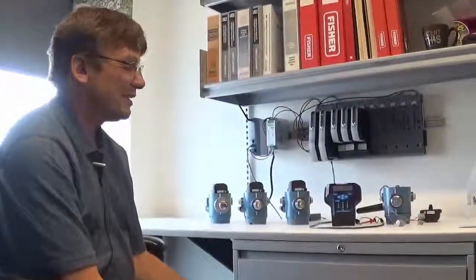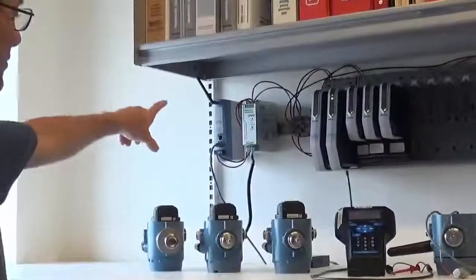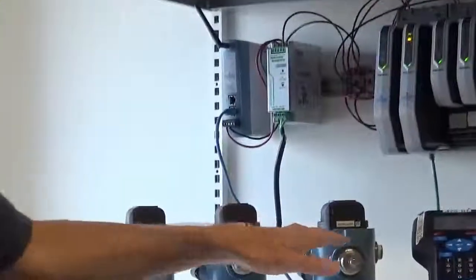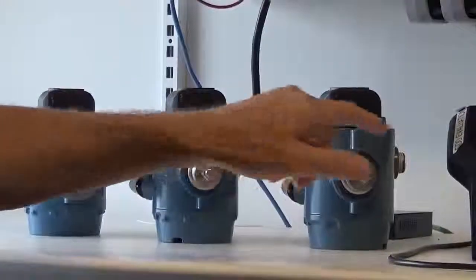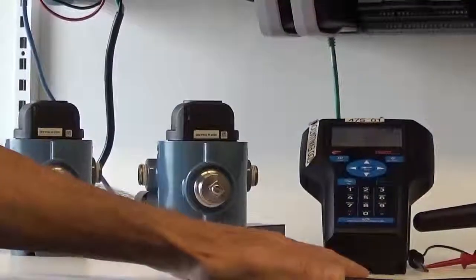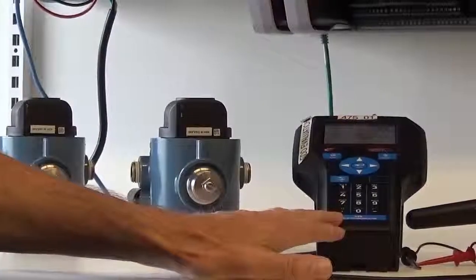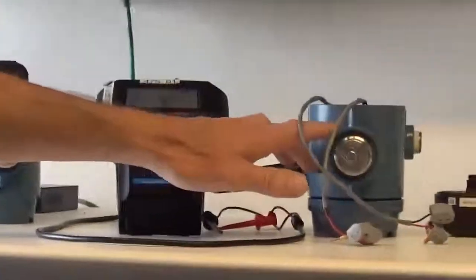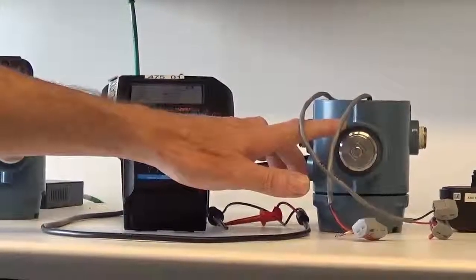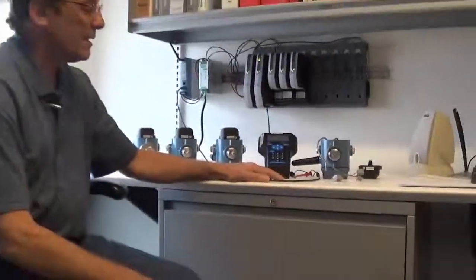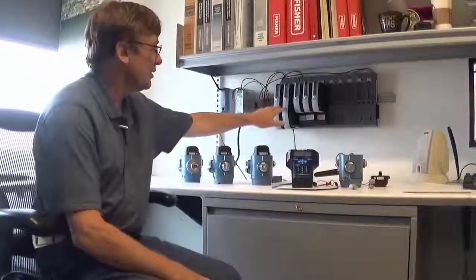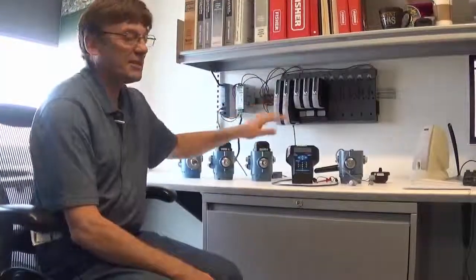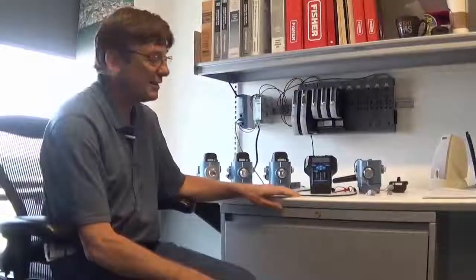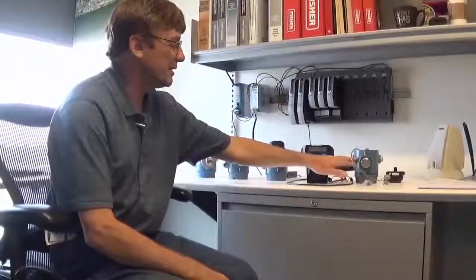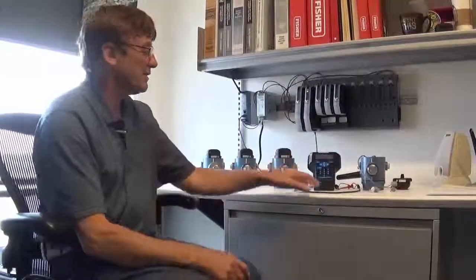This is our lab setup. Over here we have the wireless HART gateway. We have 3 commissioned wireless devices right now, and the 475 HART communicator, which we will use to configure and set up the 4th wireless HART device. Once the devices are communicating, they'll talk through this controller, and we'll set up a control strategy utilizing the measurements coming out of this device. So with that, we'll go ahead and start setting up this device.